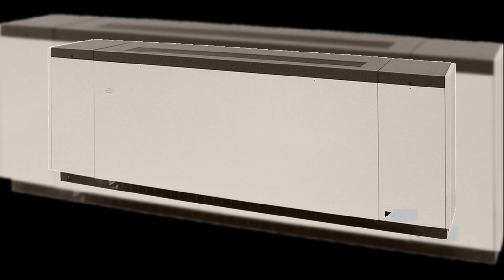Large areas like corridors, lobbies, and cafeterias require a central ducted ventilation system. Unit ventilator fans and coils should be sized to handle loads using a mix of fresh and recirculated air. Acoustics: classrooms must stay under 45 dBA, NC 40, verified by an acoustical consultant.